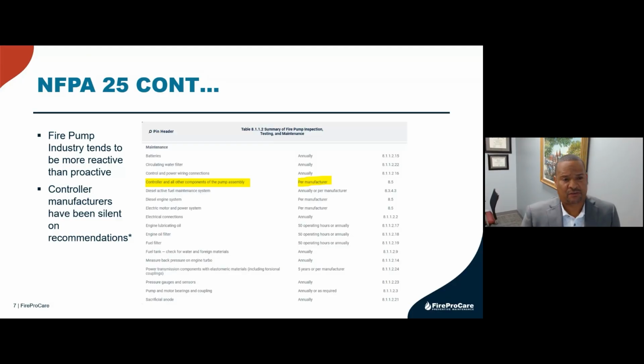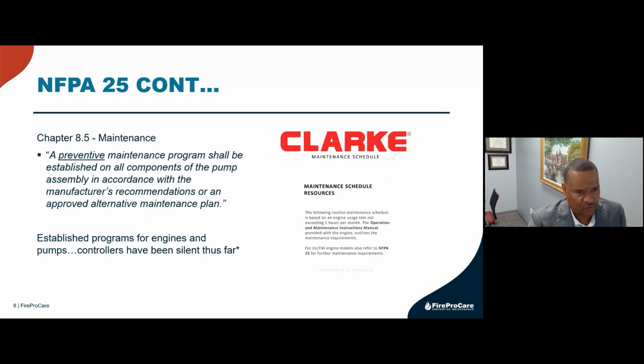Industry tends to be reactive versus proactive, and the controller manufacturers have been silent on recommendations for preventive maintenance. We want to change that. So if we take a look at chapter 8.5, notice the words again, manufacturer's recommendations. It flat out tells you here in black and white that a preventive maintenance program shall be established for everything in the pump assembly, and it should be done per the manufacturer's recommendations. Now, it does give you an open loop there where it says you can use an approved alternative maintenance plan, but that's done, in my opinion, and it was probably a good thing, because if the controller manufacturers have never published anything, the local guy can come up with something that they think works, and as long as the AHJ approves it, if there's nothing existing, then that's what you can use.